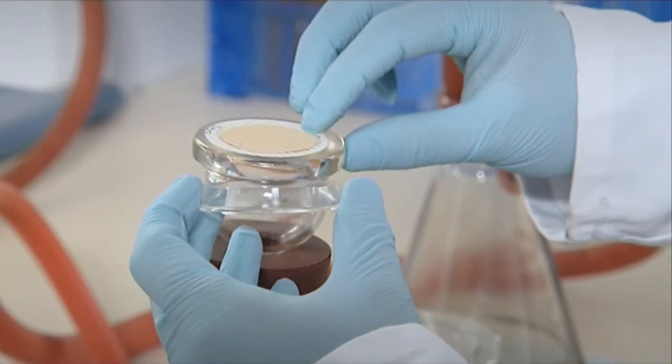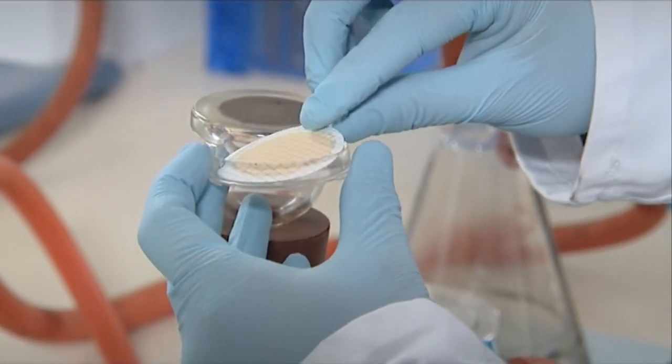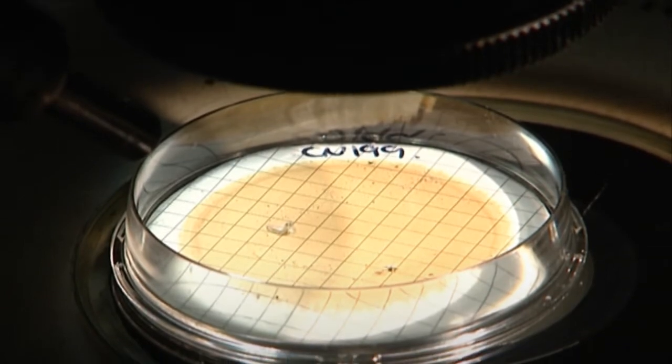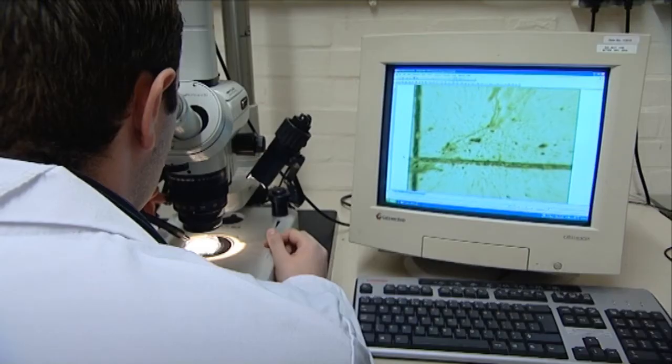We then look at the solid contamination in the oil. This is achieved by filtering the oil through a very fine filter paper and collecting that contamination. The solid contamination then is identified using an optical microscope, and here we're trying to understand the nature and also the quantity of particulate on that filter paper.